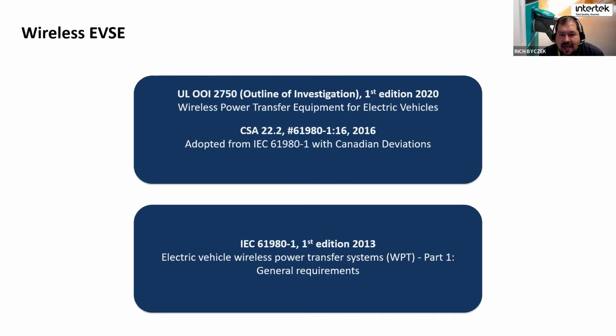Here in North America, we have the subject standard UL 2750. When I say subject standard, that means it's still in essential draft mode, but has been issued, so NRTLs can utilize that standard in conjunction with the UL 2202 and 2594 caveats. Where you have differences and can't demonstrate a conducted method of meeting a requirement, UL 2750 helps fill those gaps and shows how to evaluate that from a wireless system.